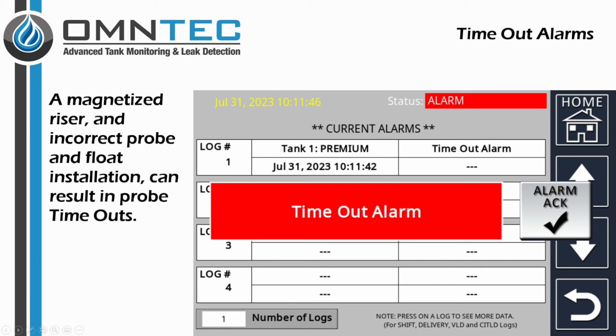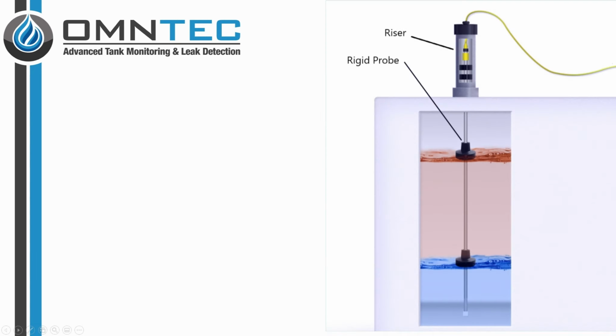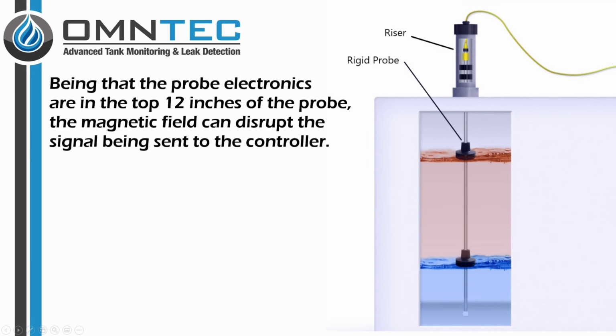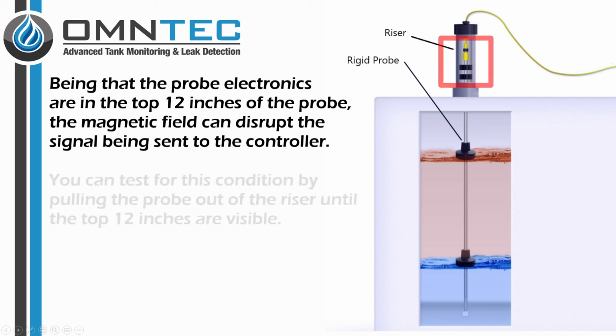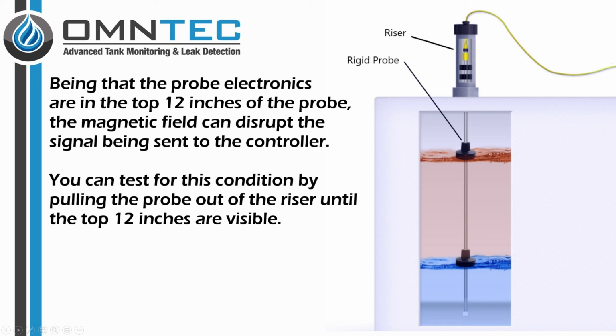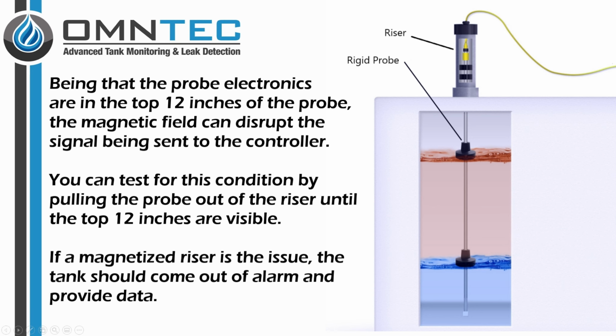A magnetized riser, an incorrect probe and float installation, can result in probe timeouts. Being that the probe electronics are in the top 12 inches of the probe, the magnetic field can disrupt the signal being sent to the controller. You can test for this condition by pulling the probe out of the riser until the top 12 inches are visible. If a magnetized riser is the issue, the tank should come out of alarm and provide data.